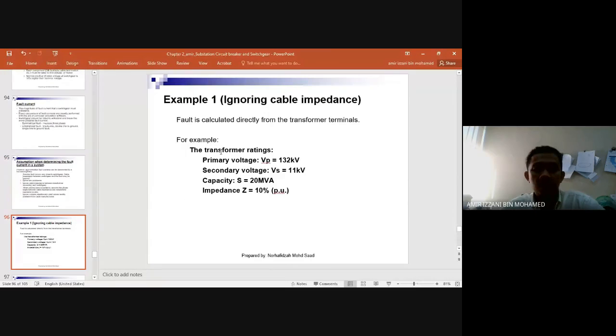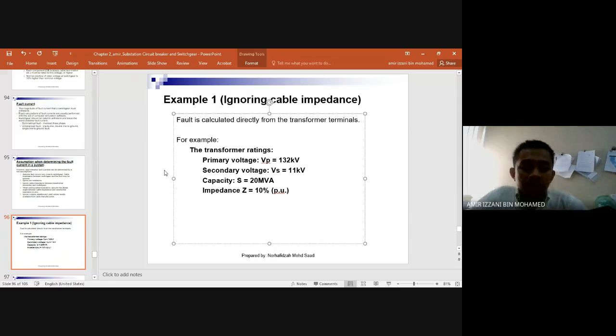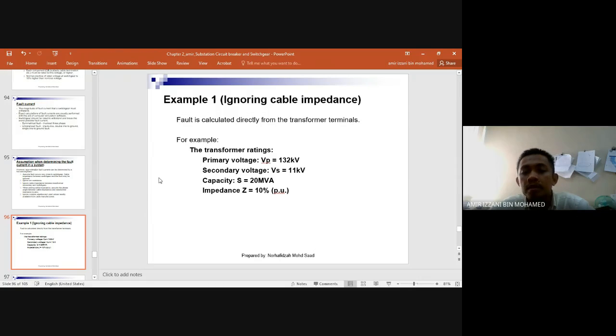Okay, let's take a look at the example. The first one is by ignoring cable impedance. For example, we have a transformer rating. Primary voltage is 132 kilovolt, secondary 11, so it's a step down transformer, 132 to 11 kV. The capacity is 20 MVA, and impedance of the transformer is 0.1 or 10%, 0.1 pu. So how can we calculate this fault current?